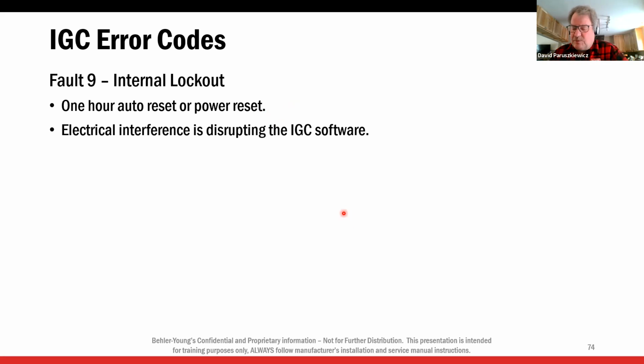And if the limit trips once, it's funny, you'll be standing at a parts counter, and a guy says, well, I changed the limit and it still trips. So he's changing it again. One bad limit off the shelf, not likely, but maybe. But two, no. If you change a limit and it's tripping again, the limit is not the problem. We need to address the problem.